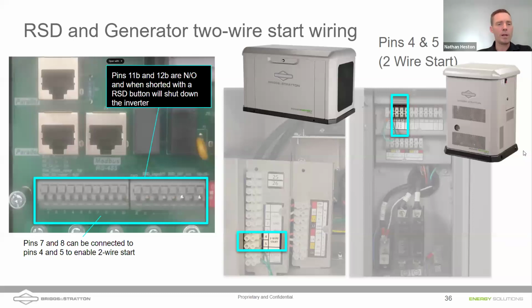Now, Daniel, we talked a little bit before about these dip switches, or these pins here. These smaller pins, these communication pins, can be used for various operations. Some of these pins are for the rapid shutdown devices. So pins 11B and 12B are for a normally open rapid shutdown device. So it's a normally open circuit. When you wire your rapid shutdown in and you depress that button, it connects those two pins and it shuts off the output of the inverter. It shuts down the solar, and it shuts down the battery output of the inverter as well.